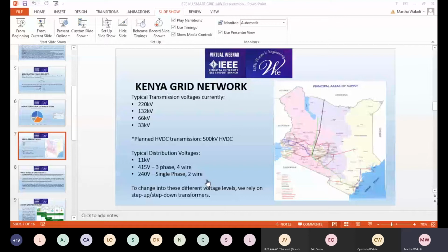Okay, so there's a black line going up towards Ethiopia. That line shows an HVDC line currently under construction by KETRACO, the government-owned transmission company. It will be Kenya's first HVDC line, and because it covers such a long distance, going all the way from Ethiopia and interconnecting at Suswa, over 700 kilometers, it needs to be at an extremely high voltage for losses to be low. Additionally, it is DC so that they can use 2 lines instead of 4, which saves on materials and makes it slightly cheaper.